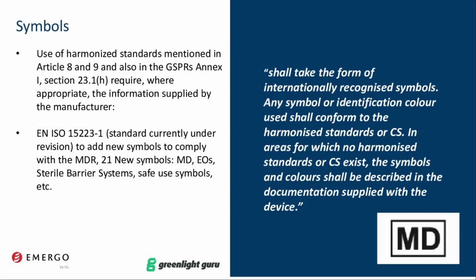So, use of harmonized standards, this hasn't changed. It's still advanced within the regulation as it was in the MDD. There is a revision of EN ISO 15223 to add new symbols to comply with the MDR. Just maybe a side comment that the symbol MD for medical devices is a requirement in the MDR to designate that a product is a medical device.